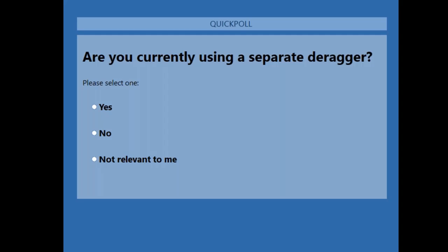John Harwood, do you want to add anything? No, I think, just to add to what you said, Mike, the biggest thing is that this is included in the drive. There are third party products out there, but there's a current monitor involved, and then you have a reversing contactor that has to be wired into the existing system. In doing our research, we've seen that those range anywhere from $1,500 to $3,000 apiece. So if you've already got a Danfoss drive, it's there. If you're looking to upgrade your system with a drive and you're having such issues, we have it built in and available. So just please keep this in mind.